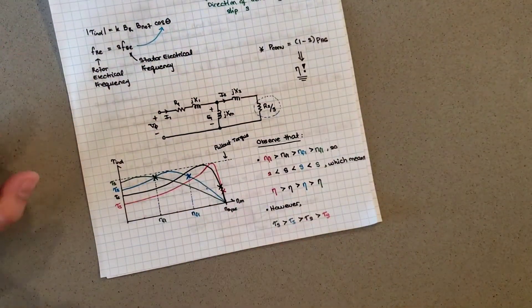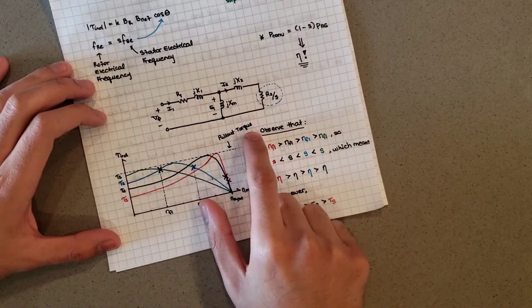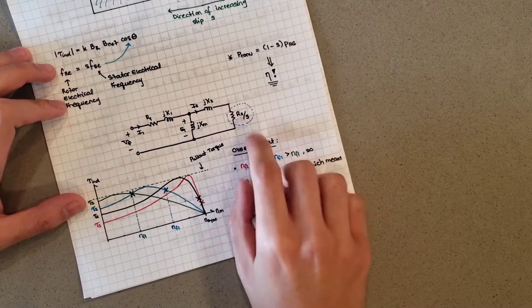What does that mean, pulling these curves? What you'll actually find is if you had a bunch of motors with the same pullout torque and same synchronous speed, then the only thing that varies between them is this r2 value. By changing the r2 value, I can actually vary where this peak occurs, which is something that's super useful.